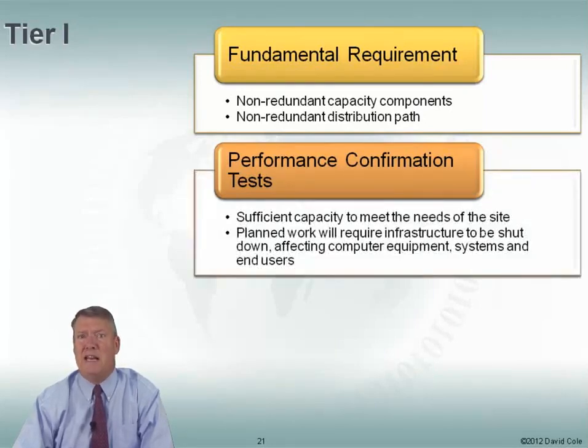I have enough capacity to meet my needs, so if I need 100 kilowatts of power, I have 100 kilowatts of power. What I don't have is a spare UPS to provide power if my first UPS goes down, or if I'm doing maintenance on it. So for any planned work, like preventive maintenance on my UPS, I have to take it offline, meaning I don't have a UPS ready for my equipment. If I get a power outage during that maintenance, all of my servers will go down, which can affect my computer systems, end users, and applications.